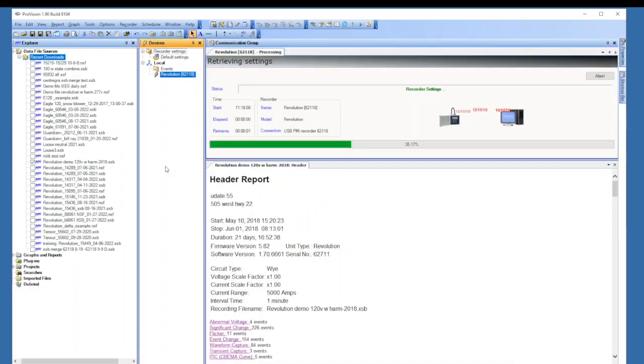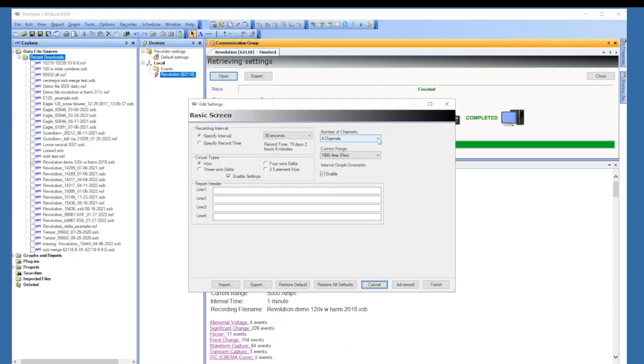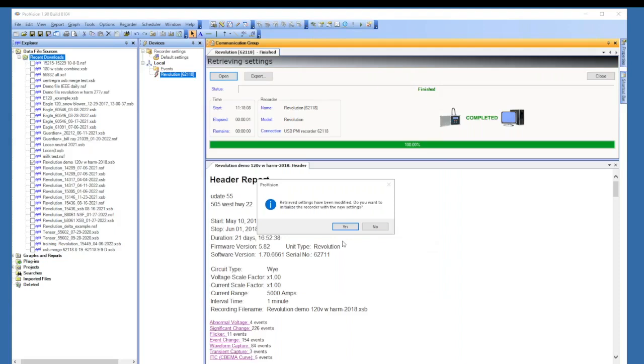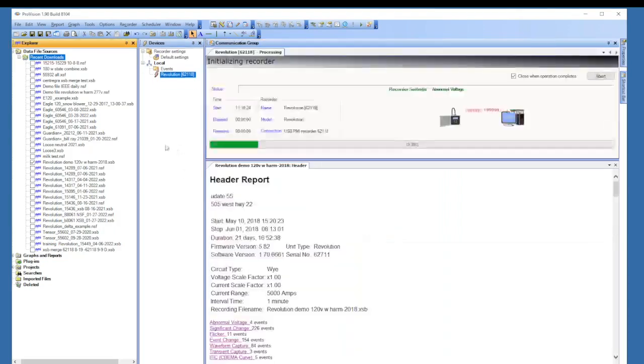So where does this information get set up? Well, there are several different ways. If you download a recording and then say yes to initialize, it will set up that recorder with the same settings that the previous recording had. So if this is exactly how you want it set up, then that would be what your next recording would look like. You can also go in and retrieve settings. So we're pulling the settings out of the recorder. And you can go in and change those settings and then finish and initialize those settings in there.